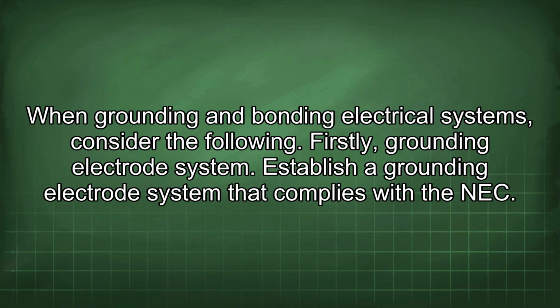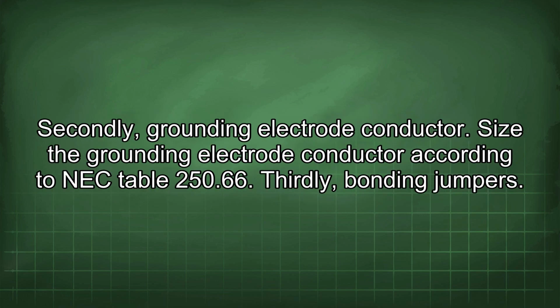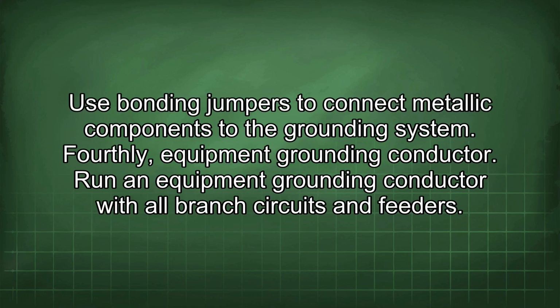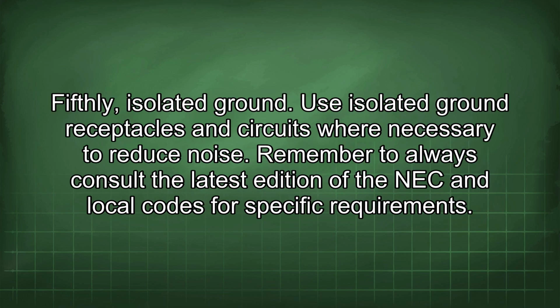When grounding and bonding electrical systems, consider the following. Firstly, grounding electrode system. Establish a grounding electrode system that complies with the NEC. Secondly, grounding electrode conductor. Size the grounding electrode conductor according to NEC Table 250.66. Thirdly, bonding jumpers. Use bonding jumpers to connect metallic components to the grounding system. Fourthly, equipment grounding conductor. Run an equipment grounding conductor with all branch circuits and feeders. Fifthly, isolated ground. Use isolated ground receptacles and circuits where necessary to reduce noise.